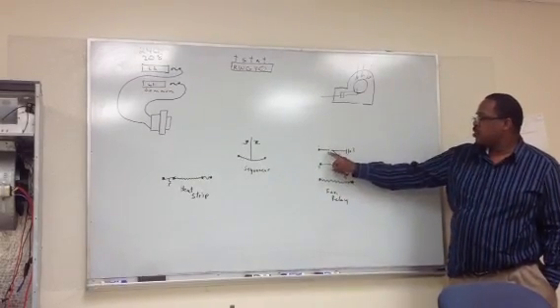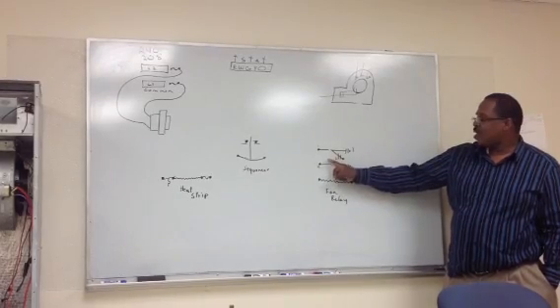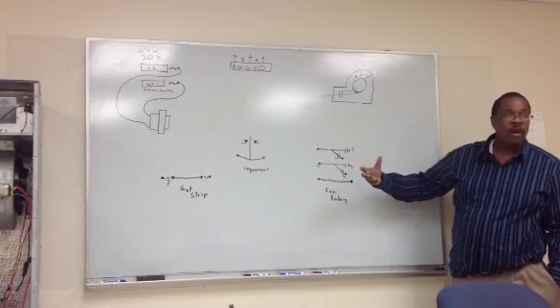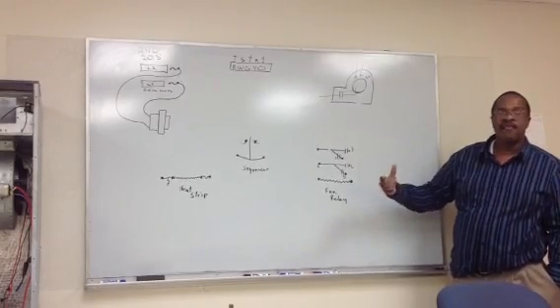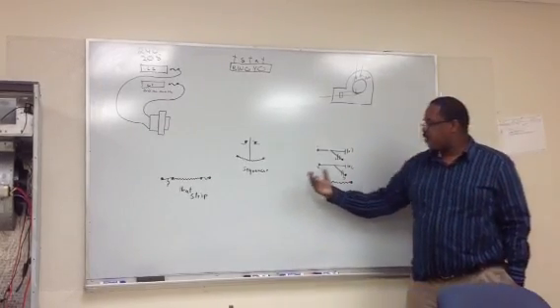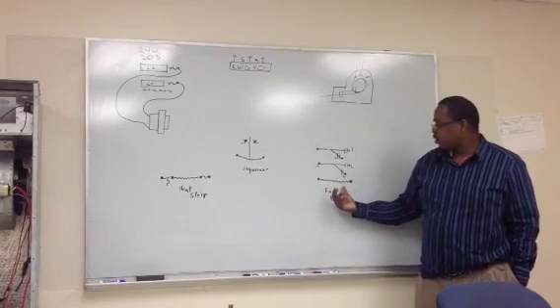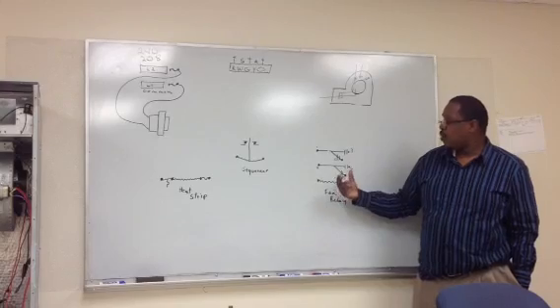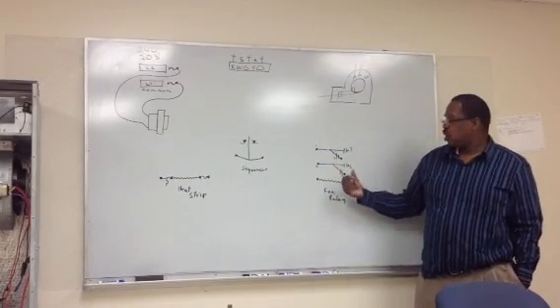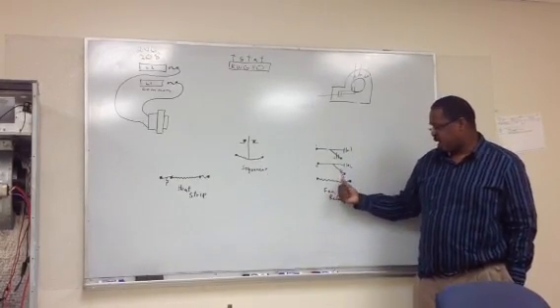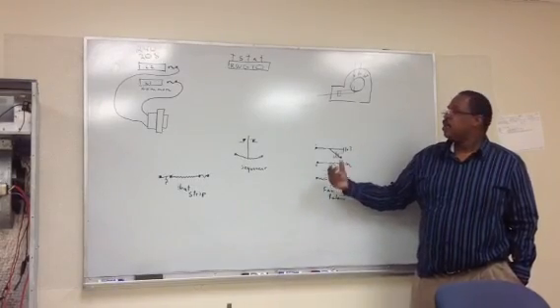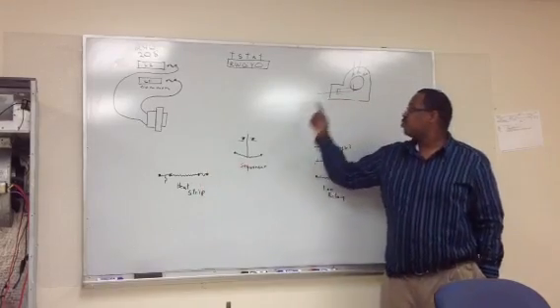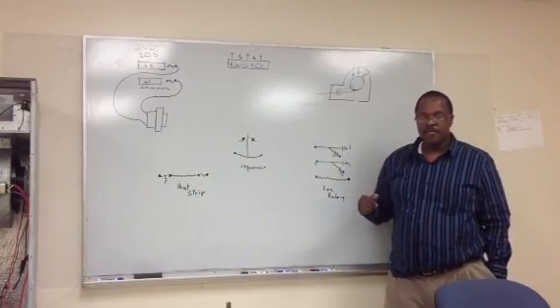And then we use this circuit to pass power. It can pass low voltage and it can pass high voltage. But for the most part, it will be controlling high voltage. So we call our fan relay and our sequencer low voltage controls in low voltage. Or we call them our low voltage loads. But in high voltage, we call our sequencer and our fan relay switches. Yes, there are switches for our high voltage because they control high voltage loads. The heat strip and the fan.